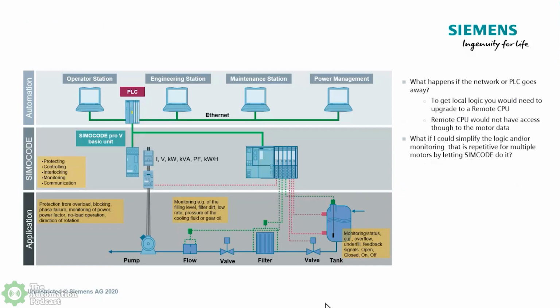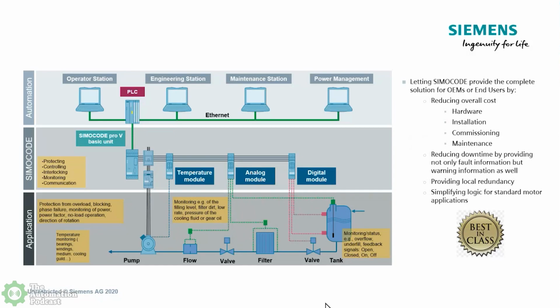With that said, I'm going to introduce the SIMOCODE a little bit more. It's going to take over all that IO, and again, I'm pushing this to the SIMOCODE's limits. It's reaching that with an analog module so I can see the flows coming in. Again, we're not controlling them because it's an across the line starter. And then I'm able to see the delta P. And then I put in a digital module, and now I can see the digital inputs of the tanks, and I can do an output to that valve to open or close. And now the SIMOCODE is taking care of that entire application directly.